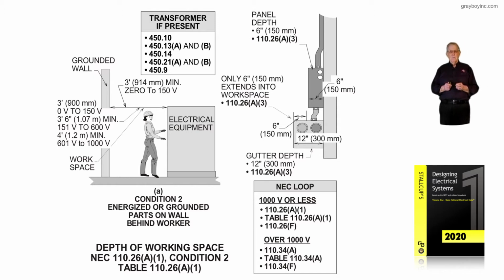It could be the disconnect in the service equipment on the primary side. It could be a disconnect located within 50 feet of the transformer's primary side, or this distance could be greater than 50 feet with a label on the transformer identifying where the primary disconnecting means would be located. 450.21 A and B talks about the size of the transformers, as I just mentioned. And 450.13 A and B, let's make sure we understand what that's requiring. It's just allowing the transformer to be mounted on the floor next to the equipment, mounted above the equipment, or mounted above a suspended ceiling in some cases, as we will see as we get on into the presentation.